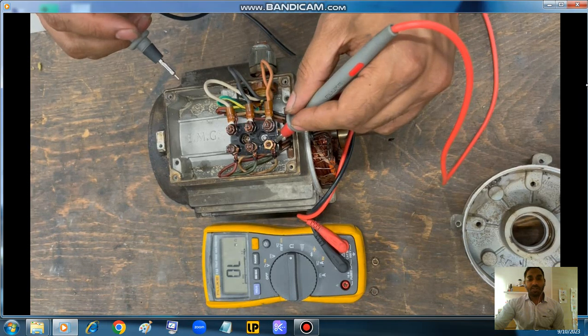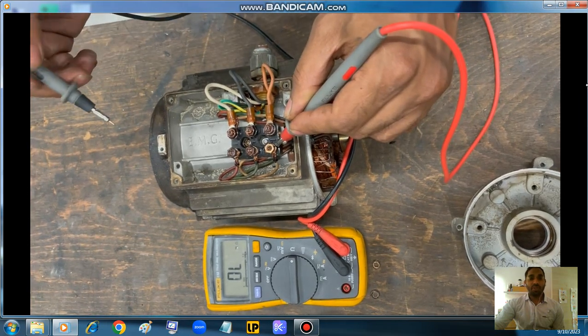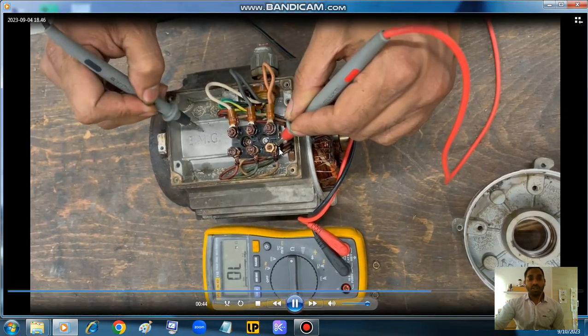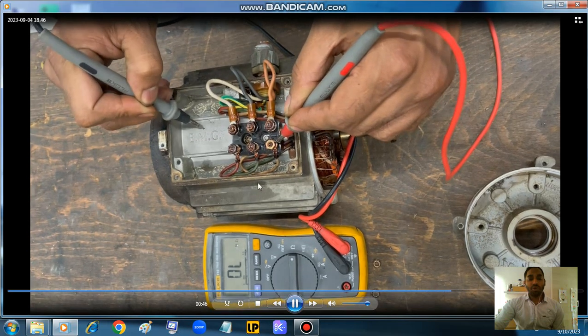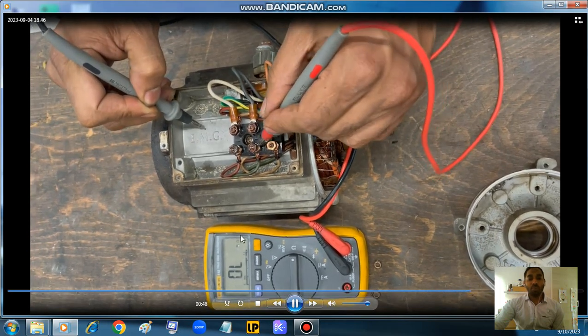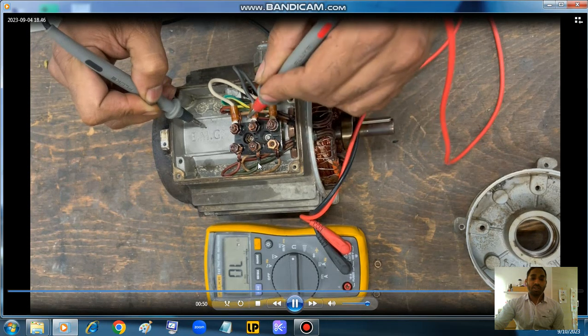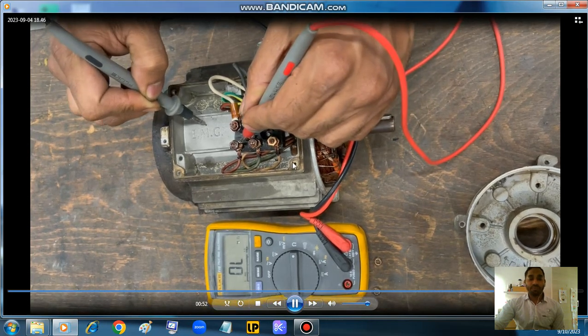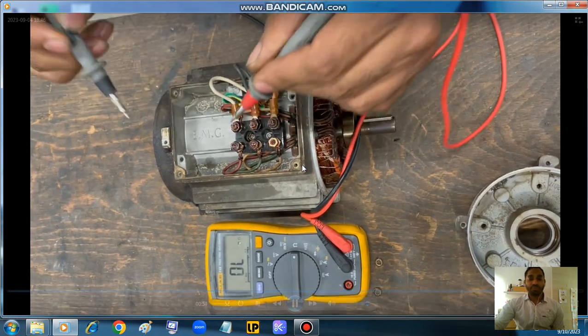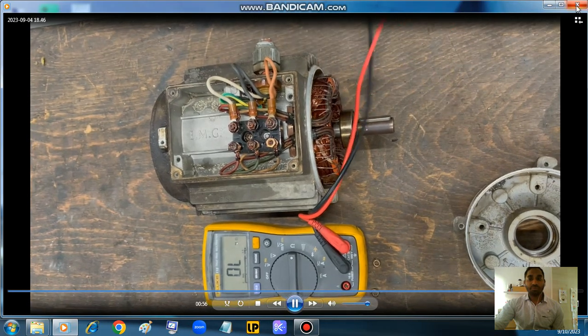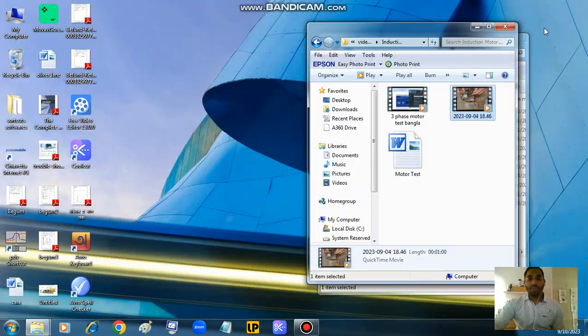Then comes the earth fault test. We put one probe in the terminal box and the other probe on the motor body, and we get an open loop here, which means there is no connection with the motor body. So all tests we found are okay here.